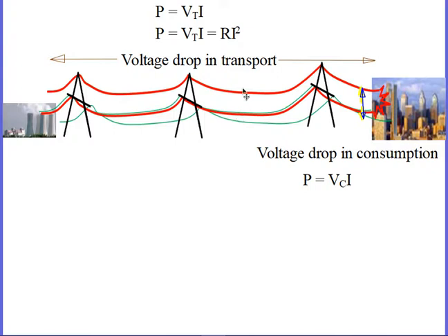In Virginia, we run at about 500,000 volts across the countryside. Out west, they do it at 700,000 volts, but there's a limit. You can't do more than that, or you'll start to get this arcing between the wires and between the wires and things in the environment. So we push it as high a voltage as we can, because that means we're going as low a current as we can. That reduces the power loss here.